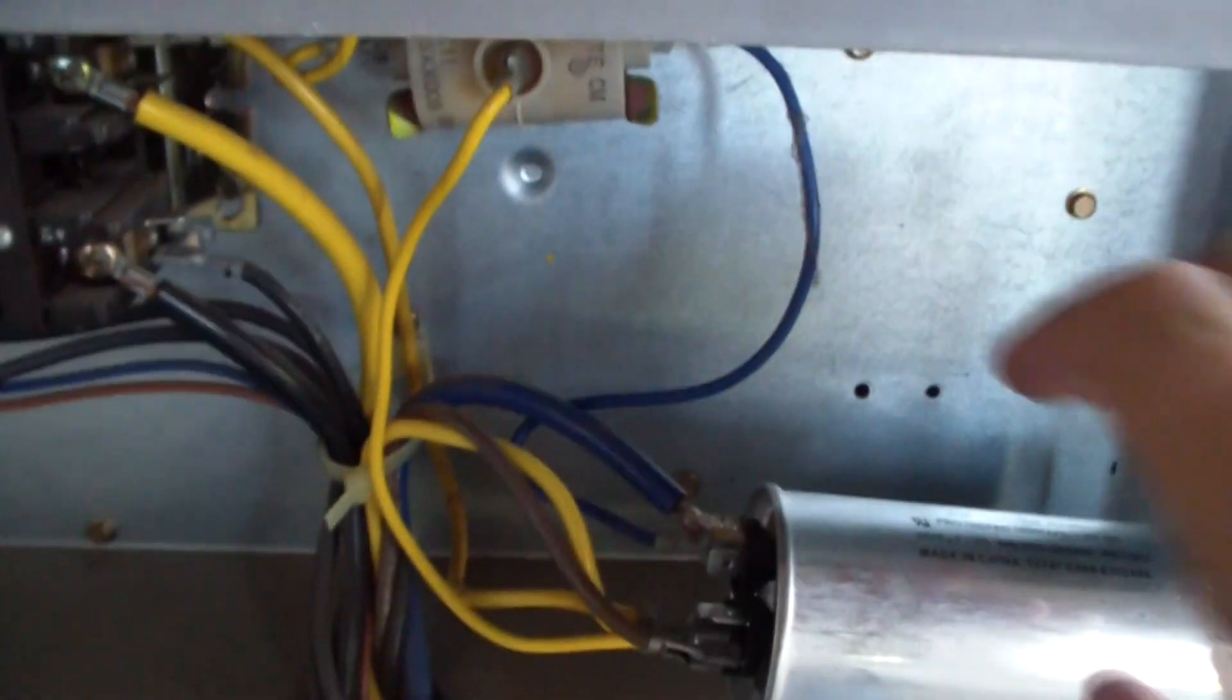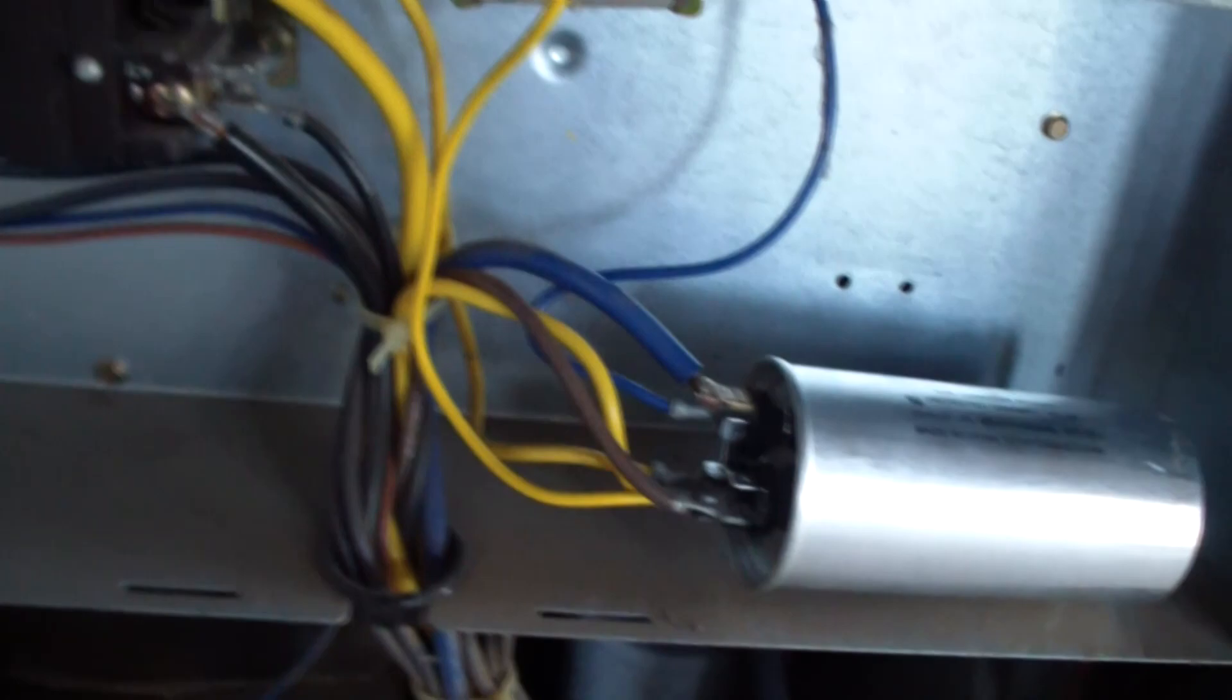She's all hooked up. It was just that easy. You can see all the yellows are going to common. The brown is going to fan, and the two blue wires are going to Herm. And everything should work.